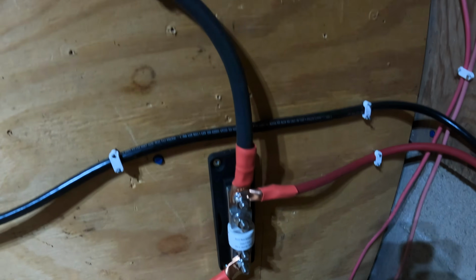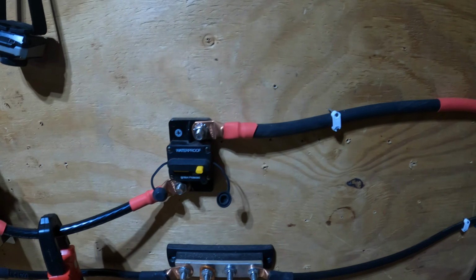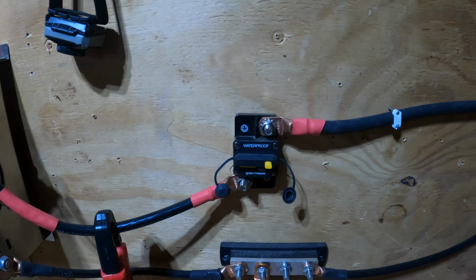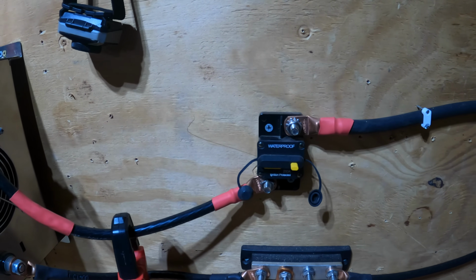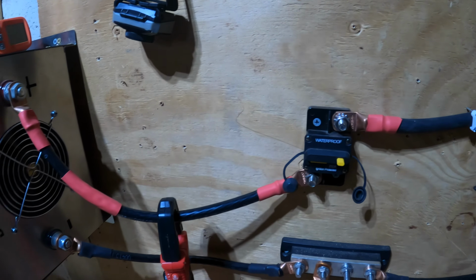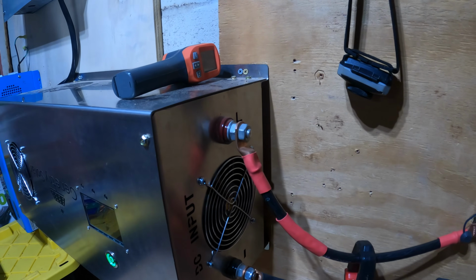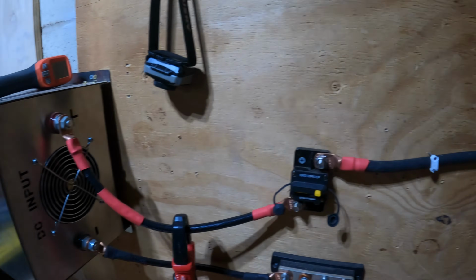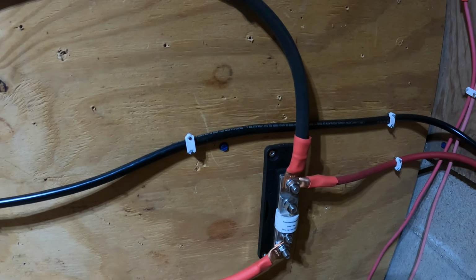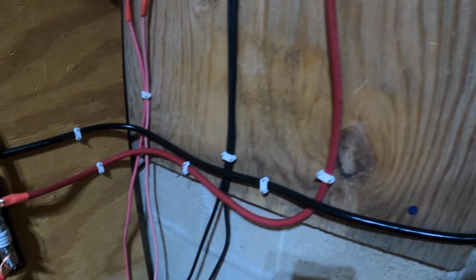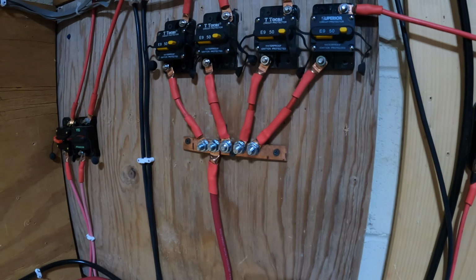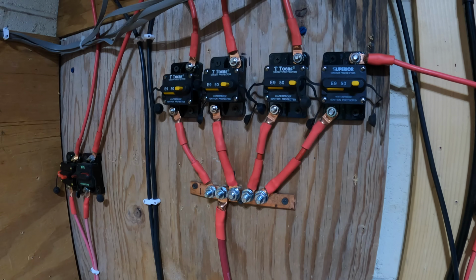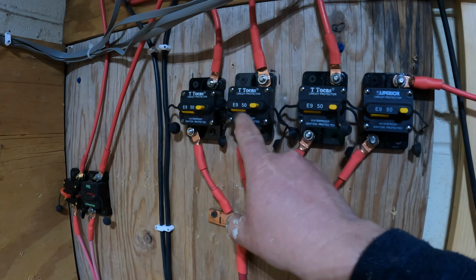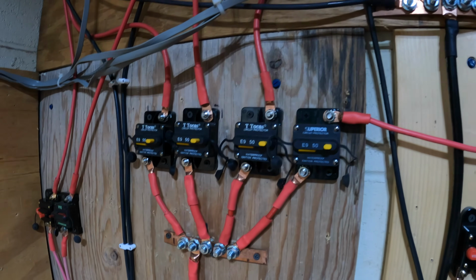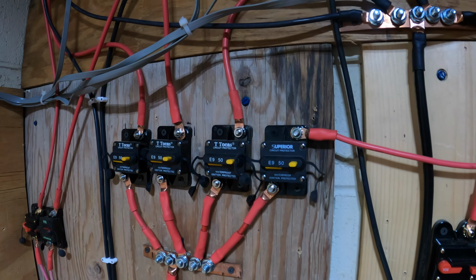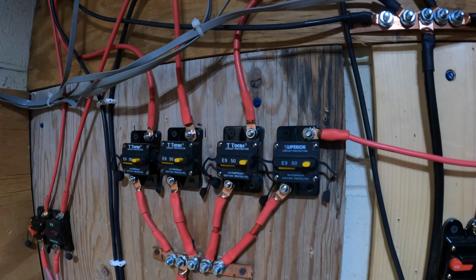Then I have this wire, the positive wire goes here. This is just an extra thing I have, not required, but I added an extra circuit breaker, and from there it goes into the positive side of my inverter. Back over here, the Class T on that side goes out to this bus bar, which distributes the positive side of my charge controllers, and I can physically separate any charge controller if I want to do maintenance, repair something, or just turn something off.